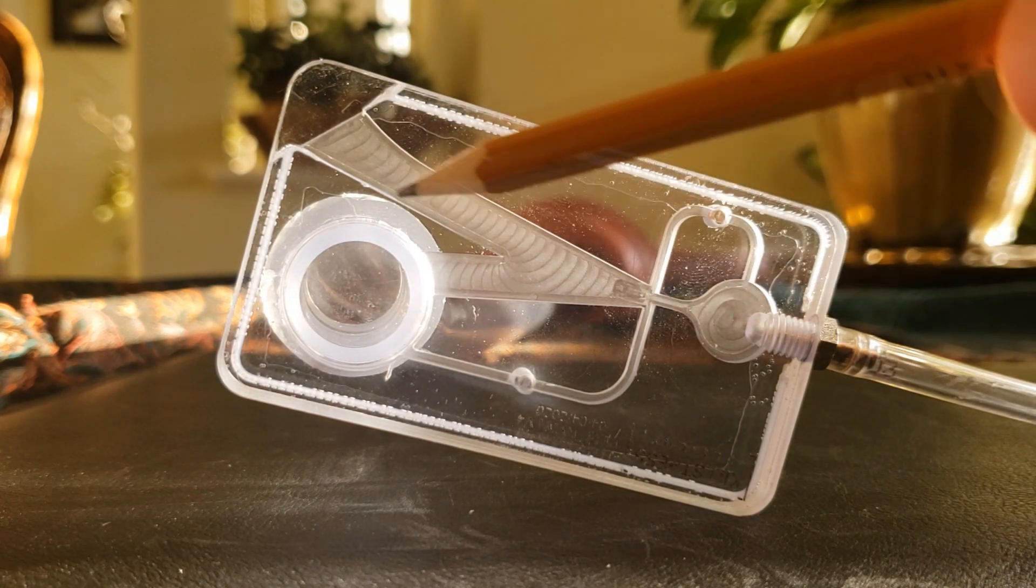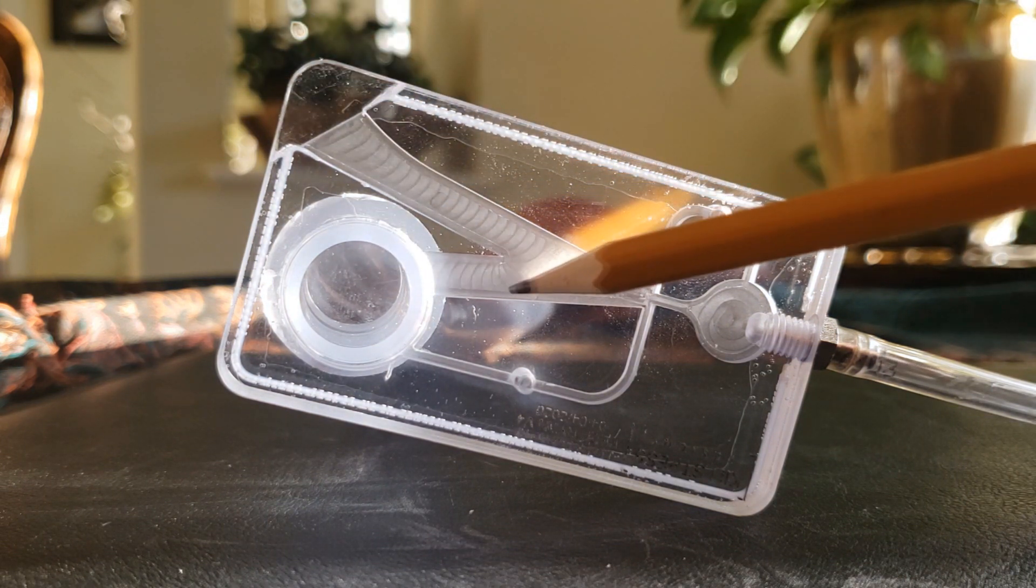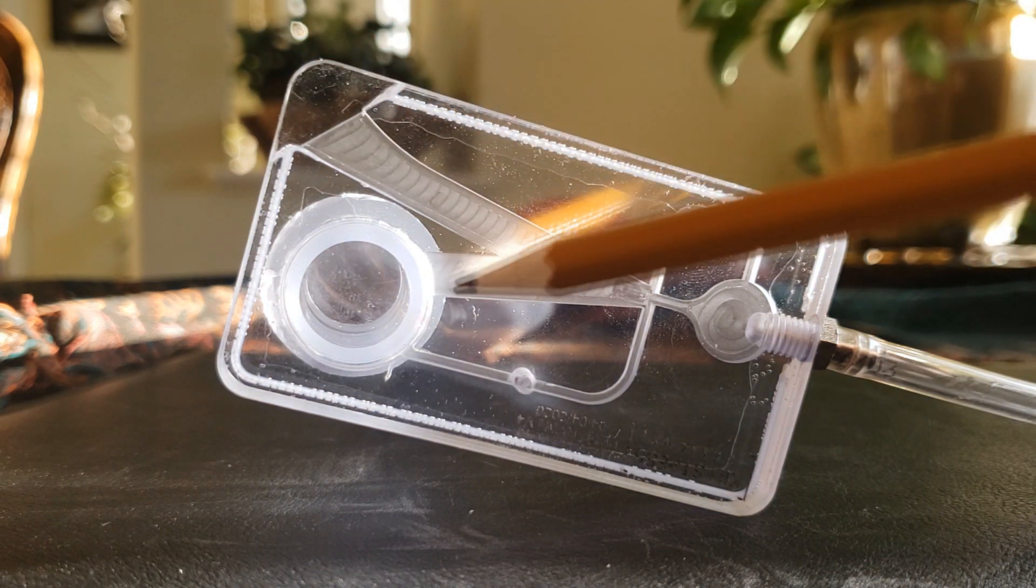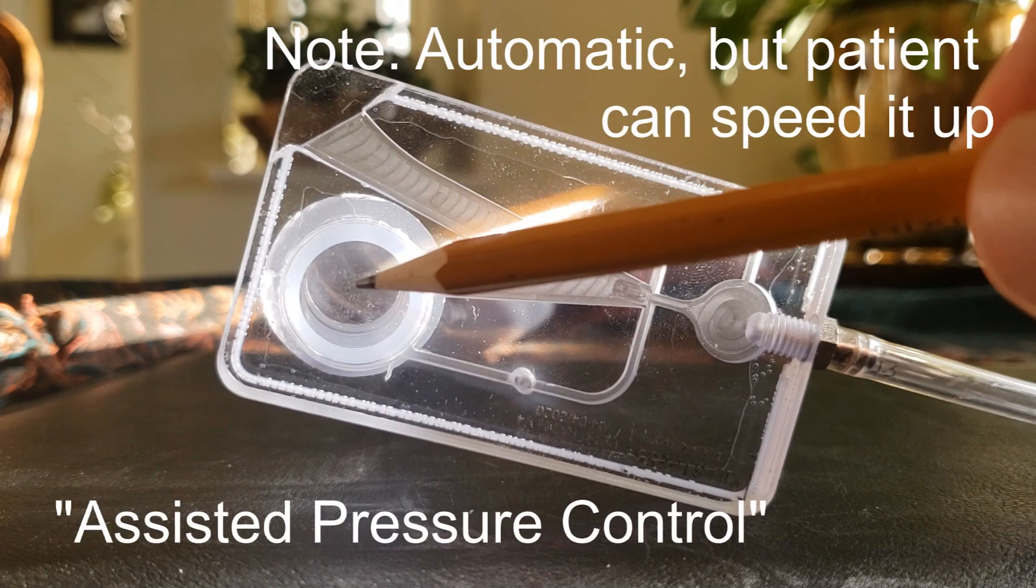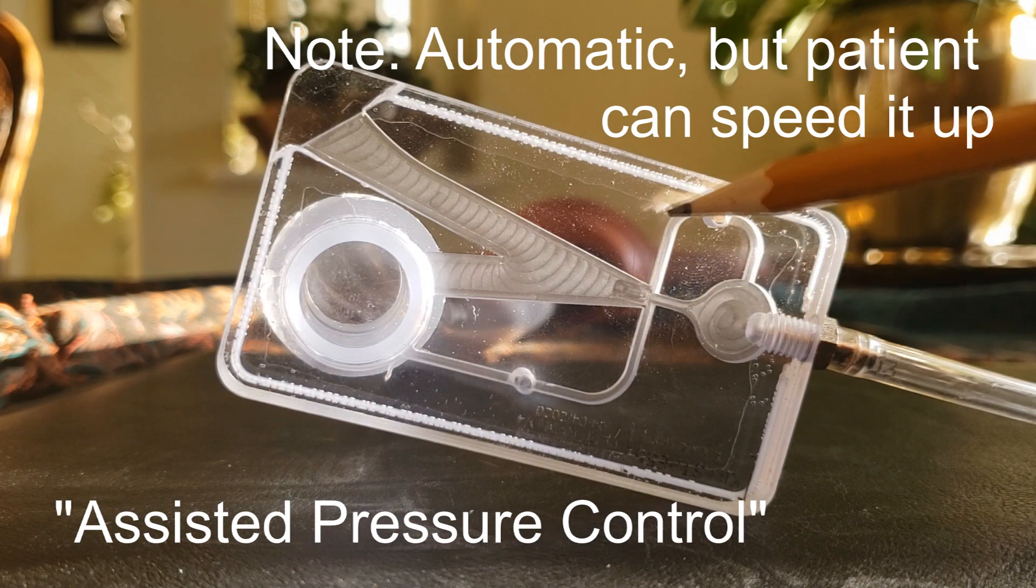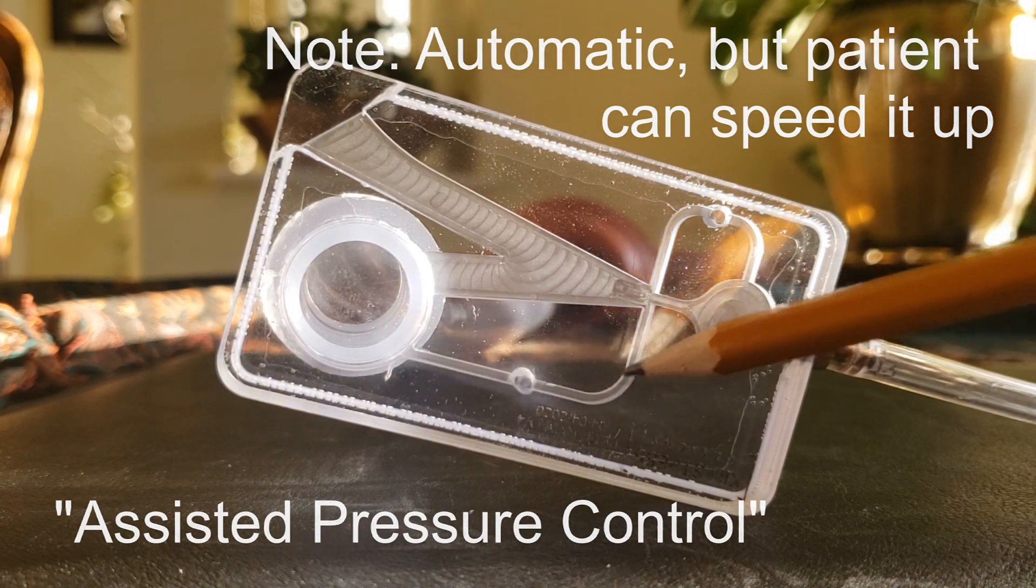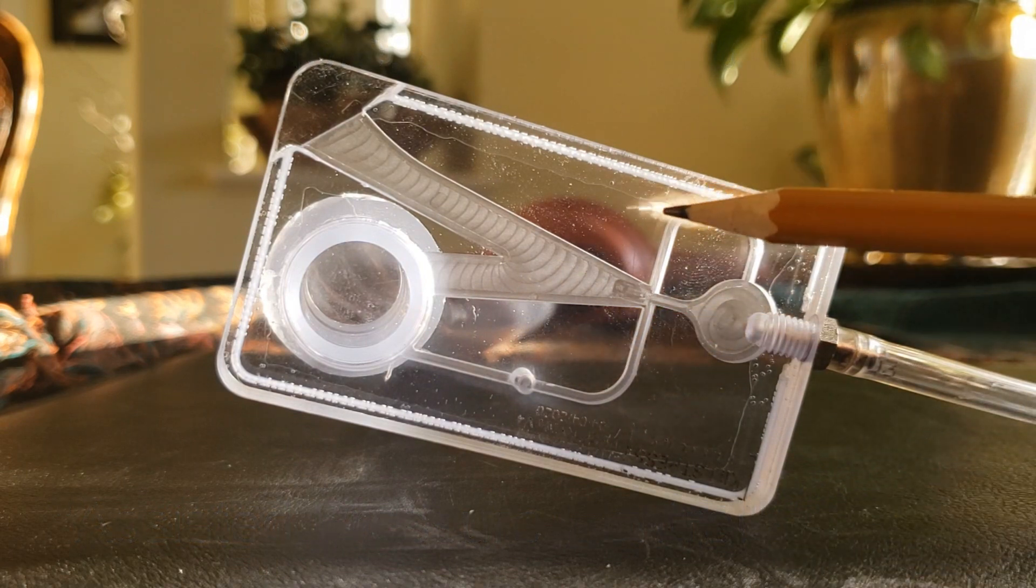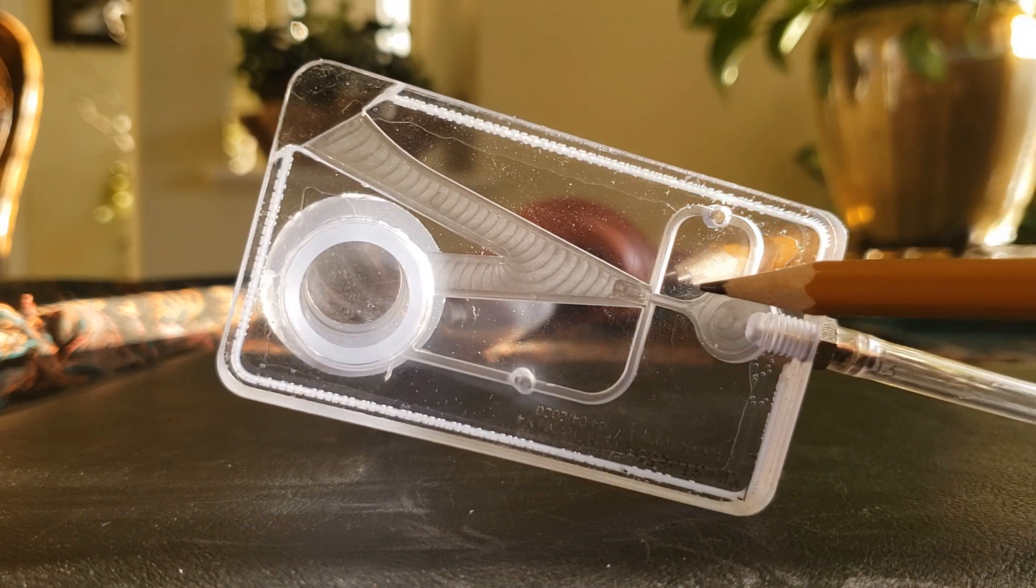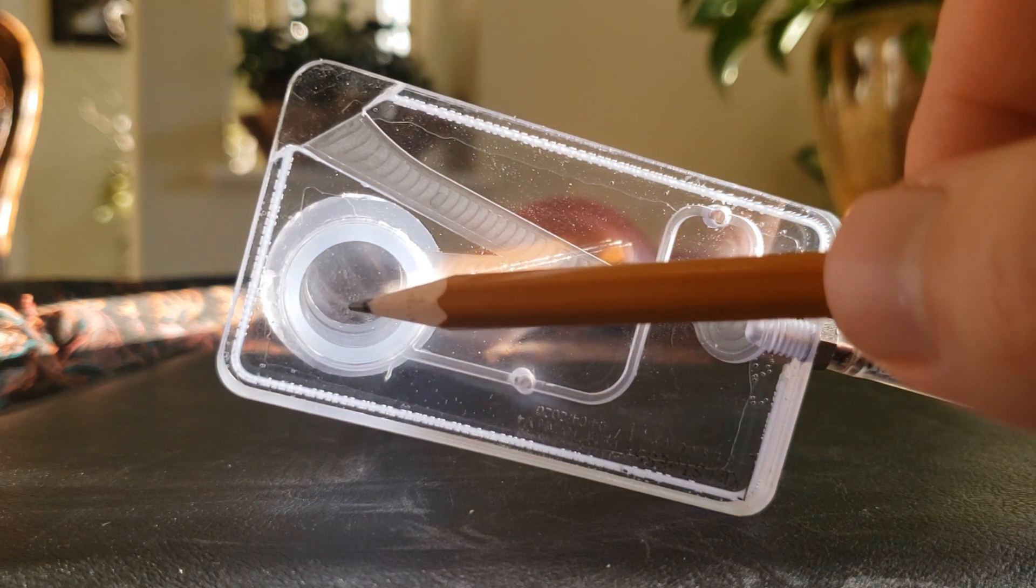As the high pressure air shoots out the exhalation channel, the air in the lungs is sucked out and eventually it reaches a low enough pressure that the difference between this high pressure side and this now low pressure side creates a flow from the right to the left, pushing the high pressure stream back to the lungs and restarting the cycle.